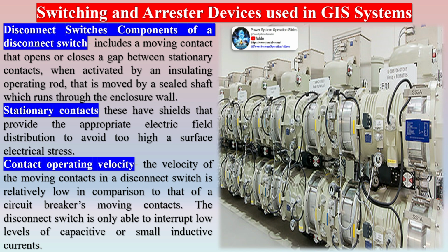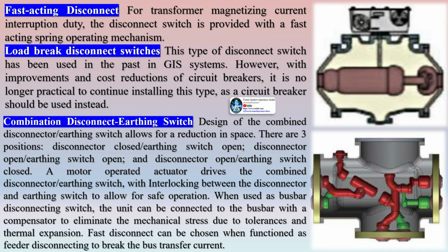Disconnect switches. Components of a disconnect switch include a moving contact that opens or closes a gap between stationary contacts, when activated by an insulating operating rod that is moved by a sealed shaft which runs through the enclosure wall. Stationary contacts have shields that provide the appropriate electric field distribution to avoid too high a surface electrical stress. Contact operating velocity. The velocity of the moving contacts in a disconnect switch is relatively low in comparison to that of a circuit breaker's moving contacts. The disconnect switch is only able to interrupt low levels of capacitive or small inductive currents. Fast-acting disconnect. For transformer magnetizing current interruption duty, the disconnect switch is provided with a fast-acting spring operating mechanism.